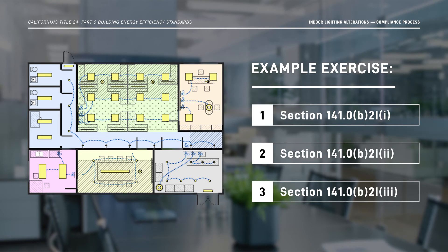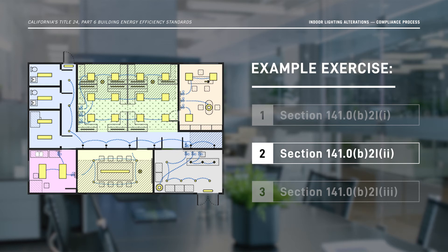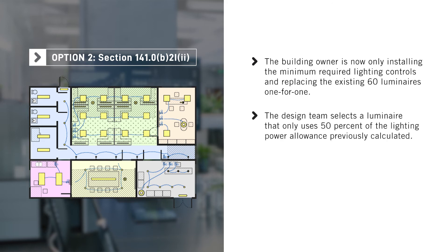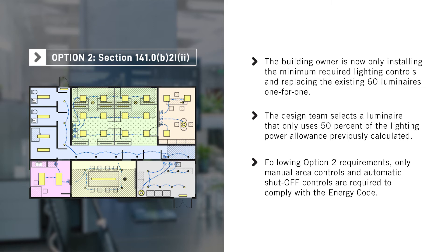Now let's walk through the same office building example using Option 2. The compliance process remains the same, but the information documented in the forms changes. In this scenario, the office building owner finds out their lighting upgrade project budget has been reduced, and now to save on project costs, can only install the minimum required lighting controls and replace the existing 60 luminaires one for one. The design team selects a luminaire that only uses 50% of the lighting power allowance previously calculated, since Option 2 only requires that the alteration project use 80% or less of the indoor lighting power allowed for new construction projects. This means that only manual area controls and automatic shutoff controls are required to comply with the Energy Code.